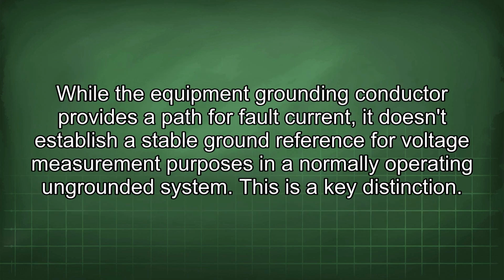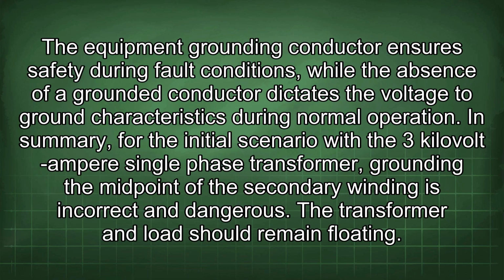While the equipment grounding conductor provides a path for fault current, it doesn't establish a stable ground reference for voltage measurement purposes in a normally operating ungrounded system. This is a key distinction. The equipment grounding conductor ensures safety during fault conditions, while the absence of a grounded conductor dictates the voltage to ground characteristics during normal operation.